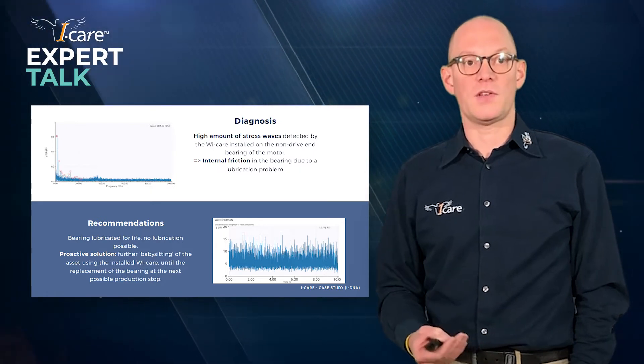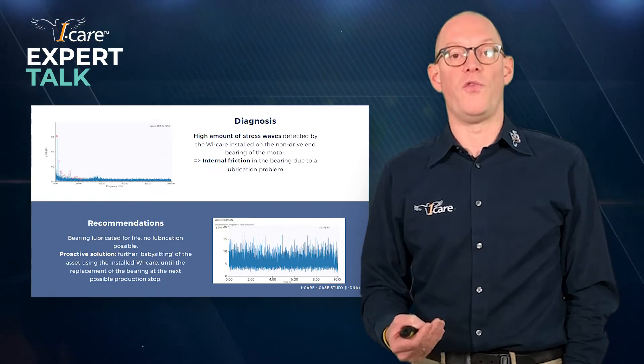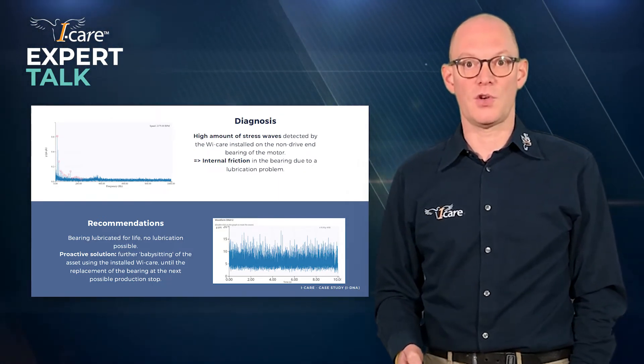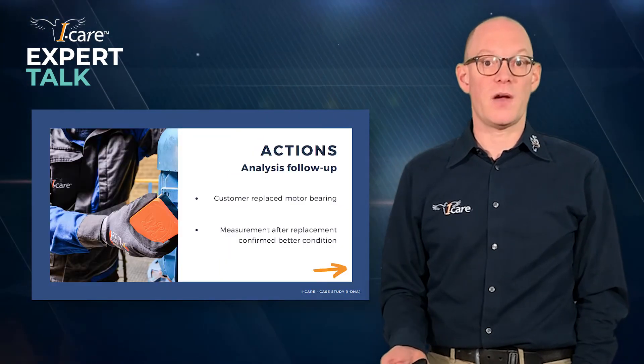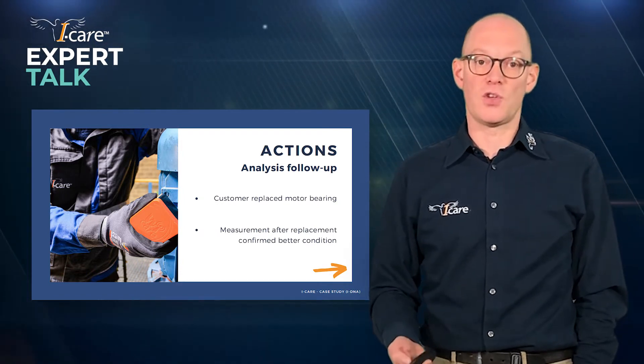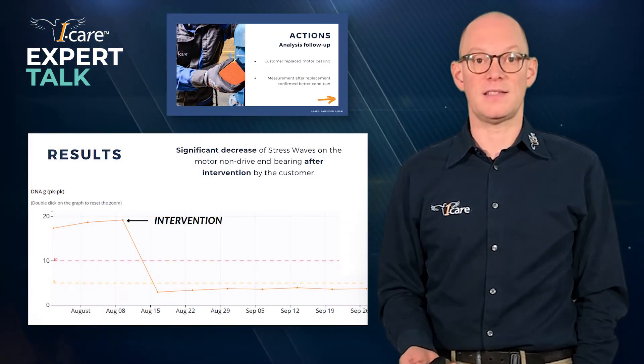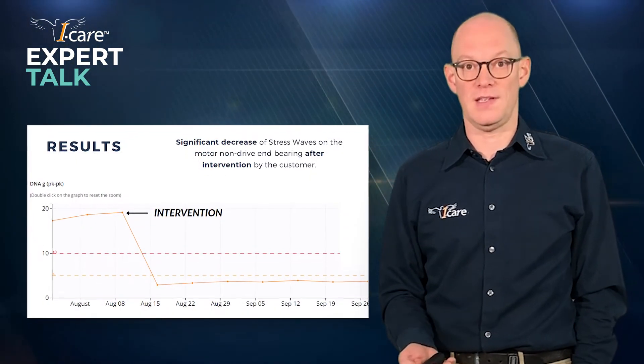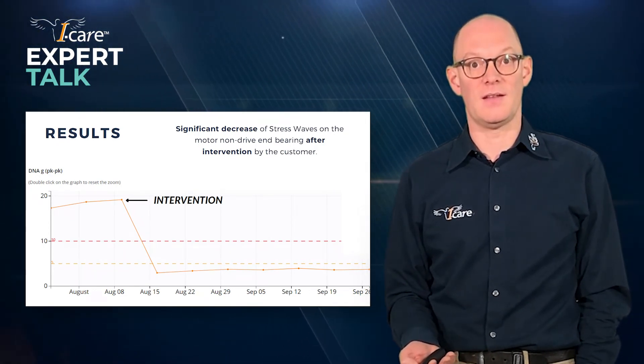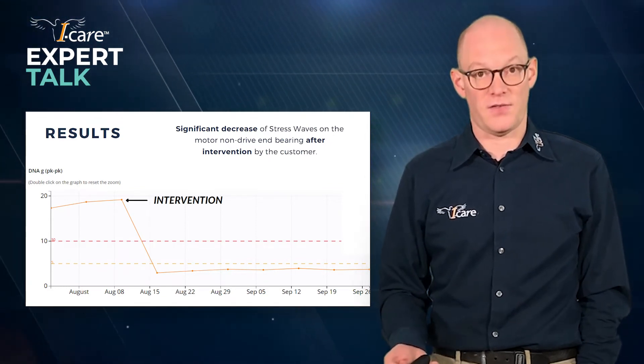So the only option left was to replace the defective — or almost defective — bearing to avoid it leading to a catastrophic failure for that asset. The customer replaced the motor bearing after our recommendation, and of course the system remained in place. After the intervention, new measurements were executed, and you can clearly see in the trend of these DNA measurements a significant decrease of the stress waves in the motor non-drive end bearing. A successful intervention.